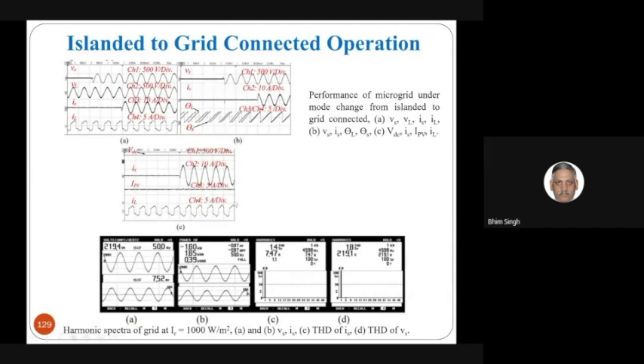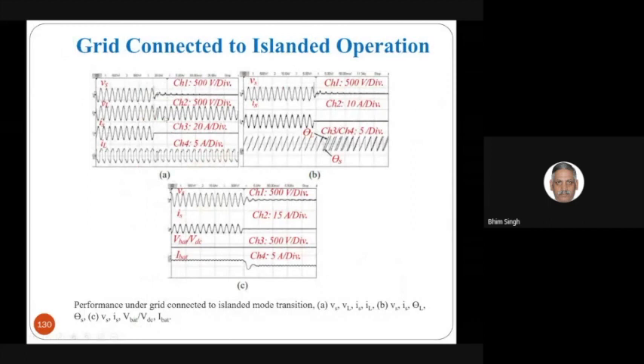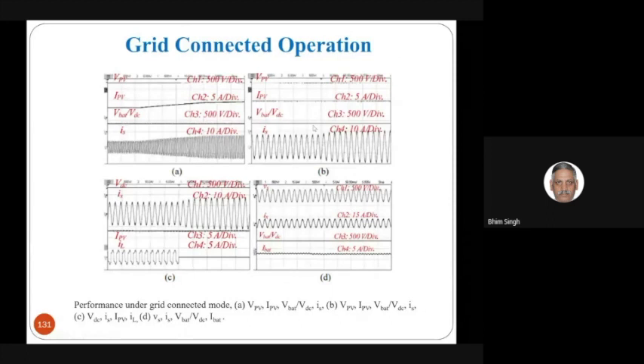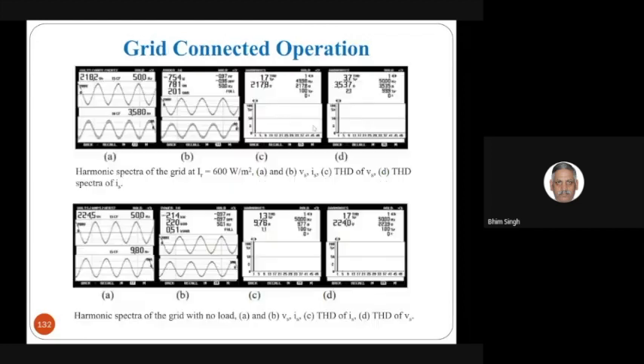So these are the typical signals during the transition from islanding to synchronization, and these are the THDs of the current and voltage on the grid, with grid current at 1.4% also. And this is when the grid is affected, but the load is not affected. Load current and load voltage are not affected. These are typical results when your solar generation is changing, and accordingly the battery is able to absorb the remaining power. So you can operate in different modes also. Here the voltage THD is 1.7% and the grid current THD is 1.3%.